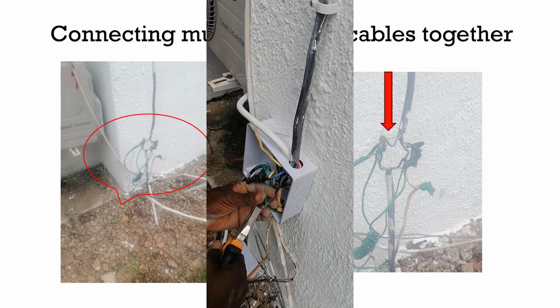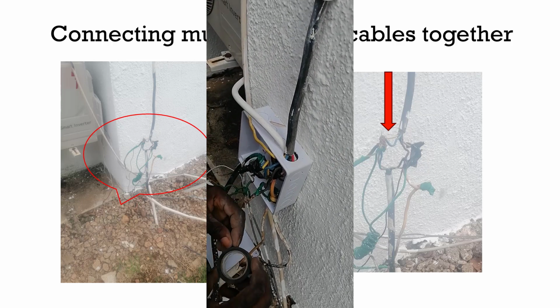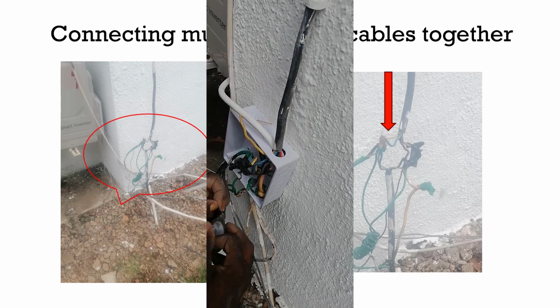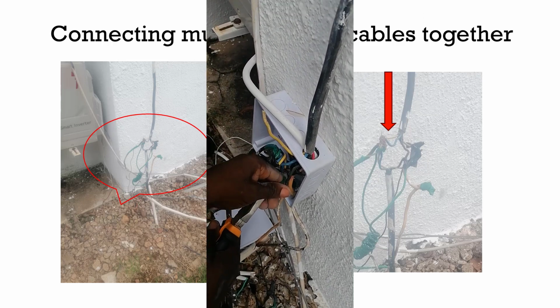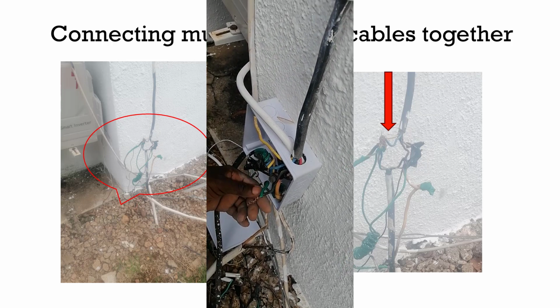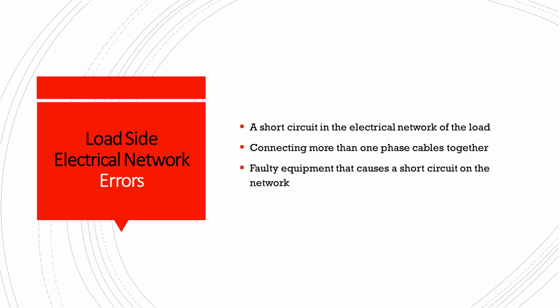In the video, you'll see how we isolated that last cable, meaning that one of those phases, two phases were actually tied together, which may be one of the causes of the error we were experiencing. So when we corrected all this cabling, all these shorts, the cabling on the distribution board, the cabling in the ceiling of that building, the cabling on this cable that supplied the other buildings, when we also isolated one phase from this three-phase cable, then we powered up the solar system.